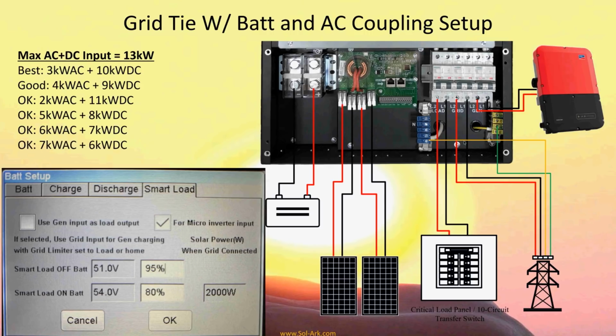Actually, let me rephrase that. If the grid is up, then this will just be a pass-through. The string inverter will simply go to the grid and also the power produced from the 8K. If we're off-grid, we need to swap these. We need to have a lower value for turning it on, so we'll turn on this connection to the string inverter at about 80% SOC or below, and then it will shut off the connection internally at about 95% or higher. And that allows us to use this in a totally off-grid situation where we can AC couple and DC couple.